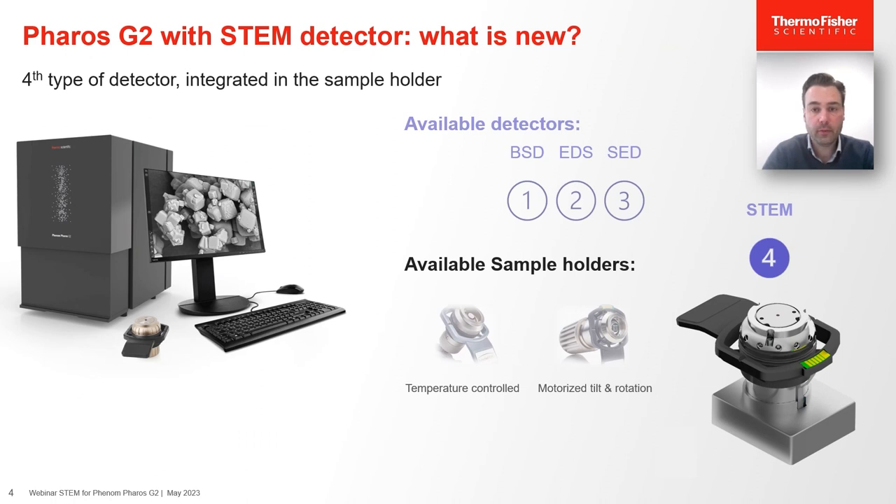This STEM detector is the novelty here — it is the fourth available detector launched alongside the backscatter detector, the secondary electron detector, and the analytical EDS detector. The interesting part is that it is fully integrated in a sample holder. The Phenom Pharos is compatible with different sample holders, such as a temperature-controlled sample holder and a motorized tilt-and-rotate sample holder, and the STEM detector is in that sense also a sample holder. Like all other sample holders, it will be fully integrated in the UI, making it very easy to use.